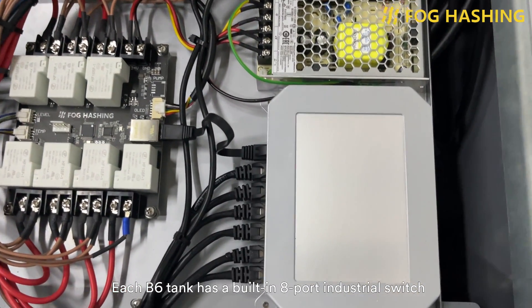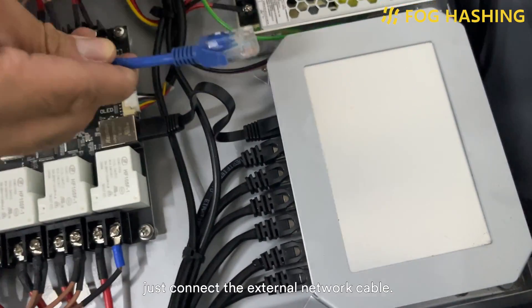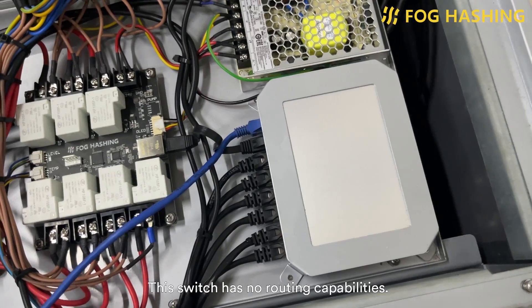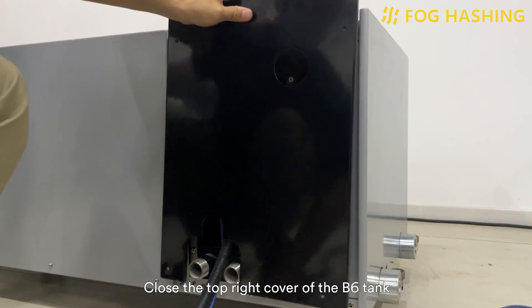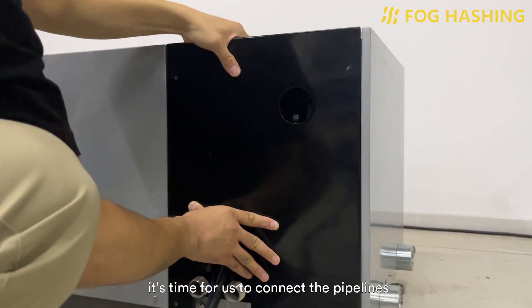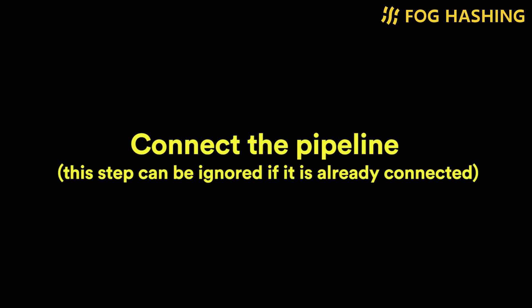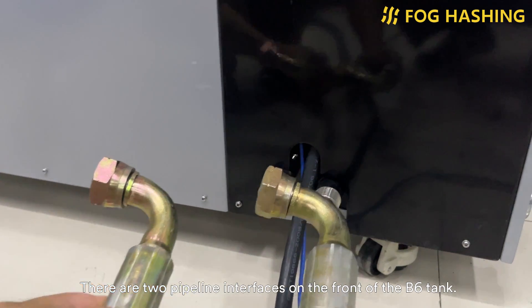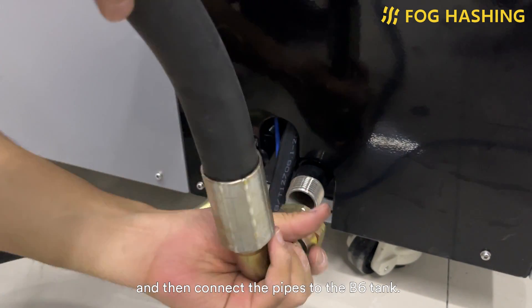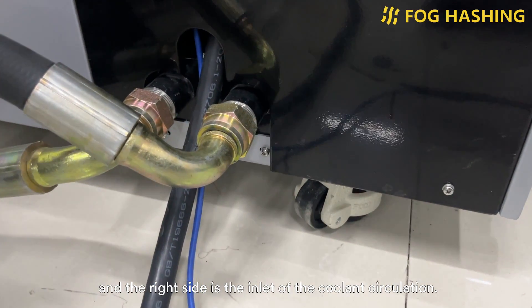Each B6 tank has a built-in 8-port industrial switch, and a network cable for the internal link to the miner has been configured. Just connect the external network cable. This switch has no routing capabilities. It's time for us to connect the pipelines — this step can be skipped if you've already done it when deploying the dry cooler. There are two pipeline interfaces on the front of the B6 tank. We put the nitrile gasket into the pipe joints and then connect the pipelines to the B6 tank. Note that the left side is the outlet and the right side is the inlet of the coolant circulation.